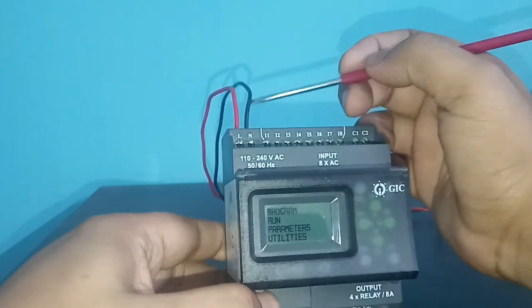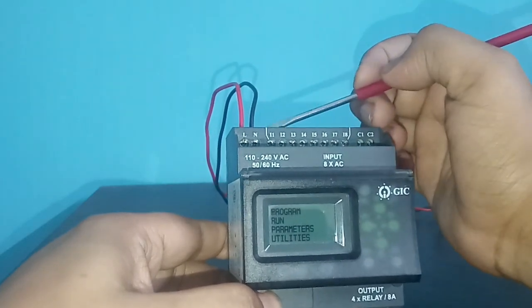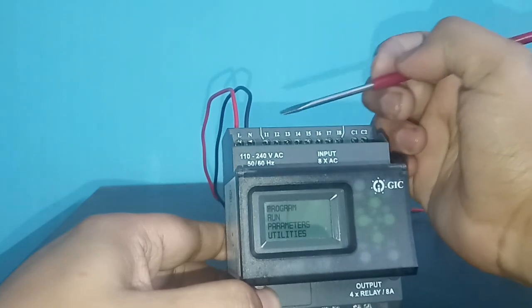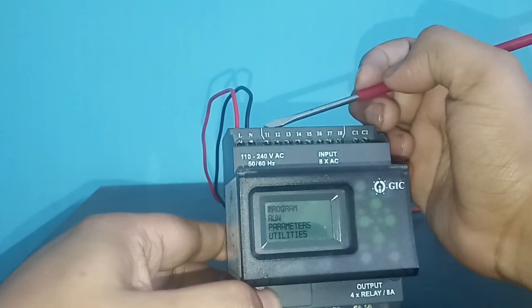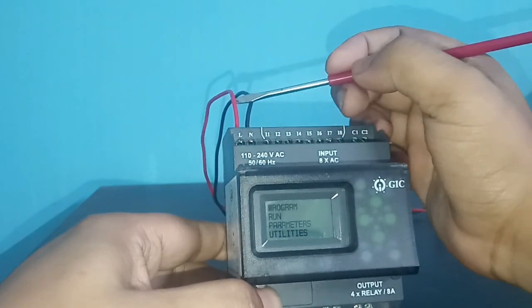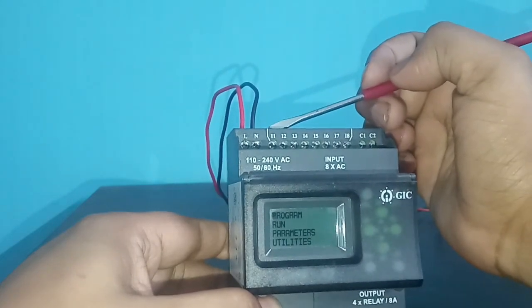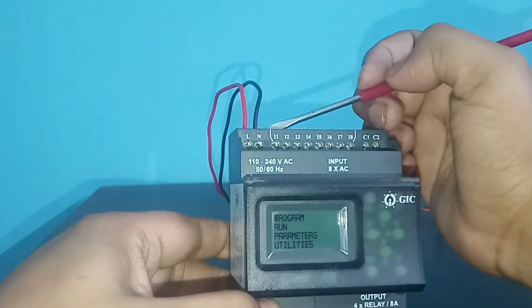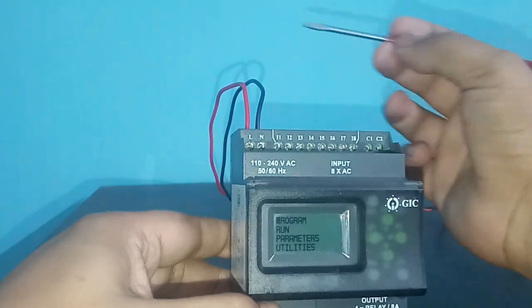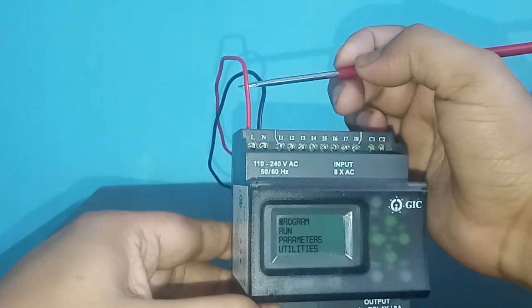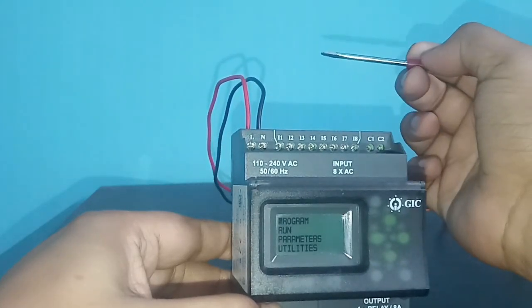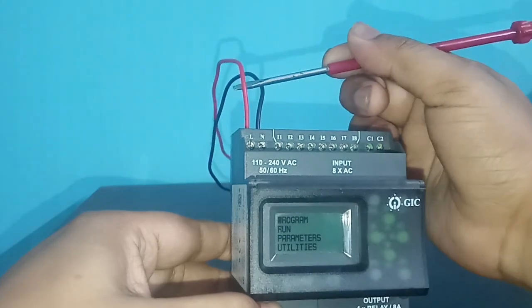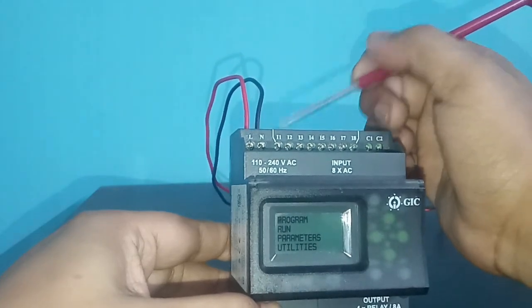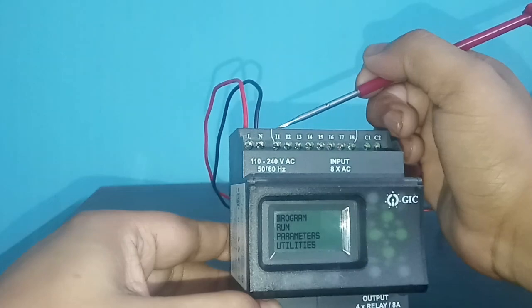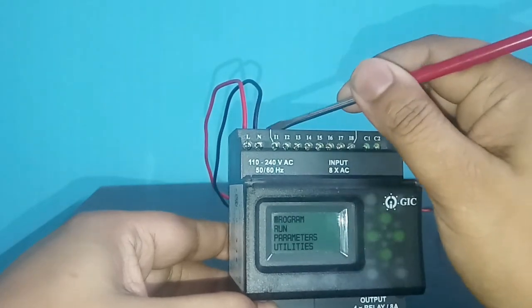Digital input simply means whether the line voltage is present here or here or here or not. So this I1 digital input is connected. That means this line voltage is present here in I1. So you can connect a field sensor output or maybe a relay output here along with this line voltage in series. So if your relay is tripped, it can get the series voltage here and it can make the circuit complete. Thereafter we can say that I1 is energized here.